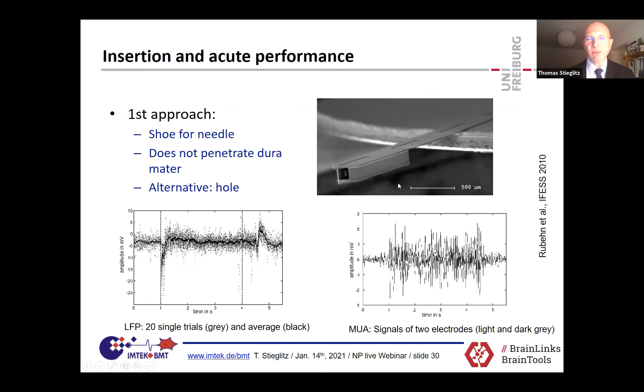It took us some years, and then we thought, well, we don't need those horseshoes. We make things very thin and flexible. Just make a hole on the tip, use a very thin tungsten wire, put the tungsten wire through the hole, push it in, and pull the tungsten wire out. And that worked well. Only thing was that I lost all the guys and girls who worked on that, and I now have to assemble all this data and publish it by myself. So keep your eyes open, but it will take some more years.